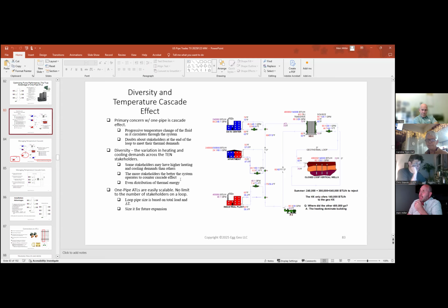All right. And these thermal energy loops are very easily scalable. There's no limit to the amount of stakeholders you can put on the loop. There is a total limit, though, of the amount of BTUs that the loop can handle. So that's why I said, when you size it, you size this for future expansion. So if you expect in the future to ultimately have 20, 30 homes on this, and as I said, 10 million BTUs, then you size it for that, okay? And if you only connect one person in the beginning, it's fine because this pump here is VFD controlled and will ramp up and down.